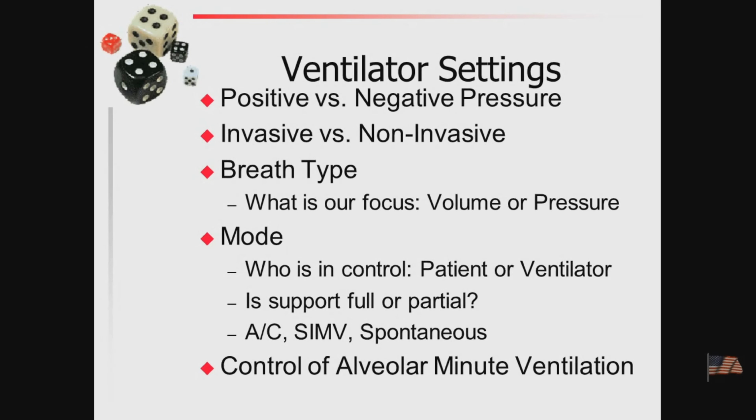The real essence of this, though, is what type of focus are we going to have when we're delivering a breath? And there's two primary ways to approach positive pressure ventilation. I can focus on giving a fixed tidal volume that's consistent from breath to breath, or I can focus on limiting the airway pressure to a preset threshold, and that's constant from breath to breath. Let me talk about each of these in a sec.